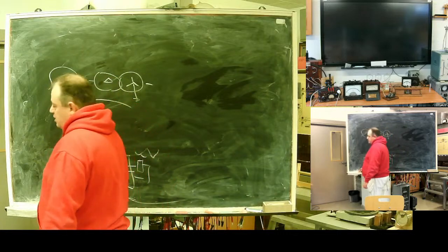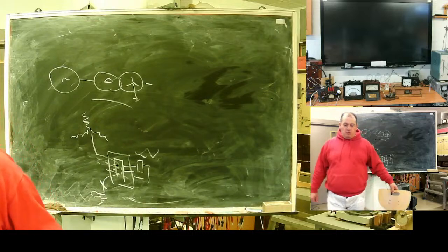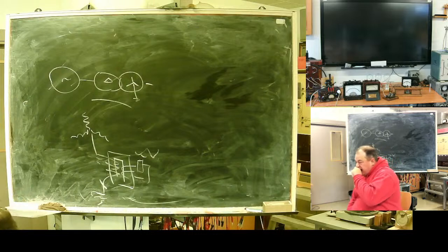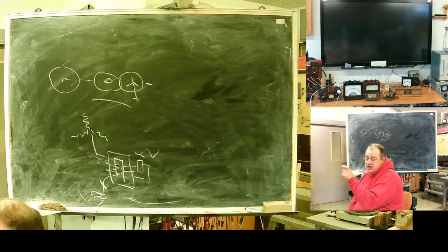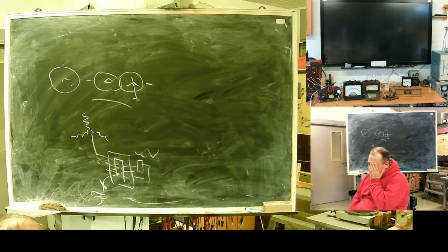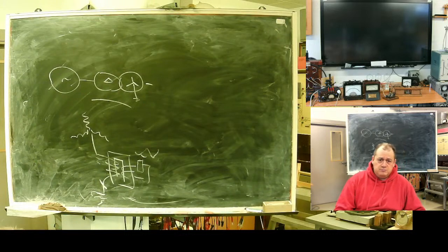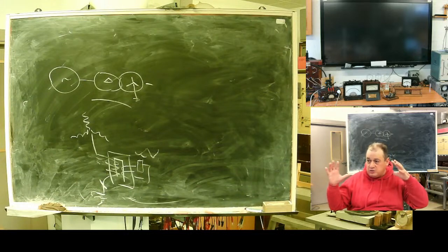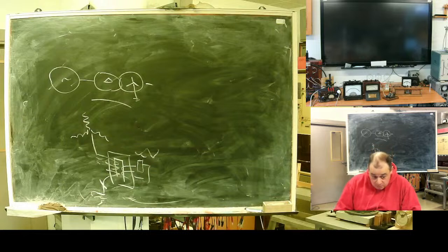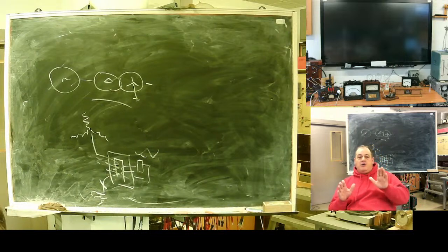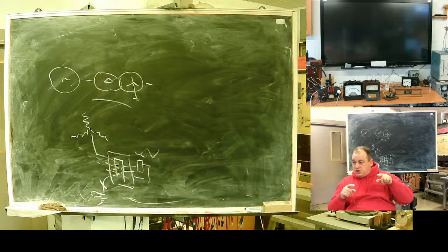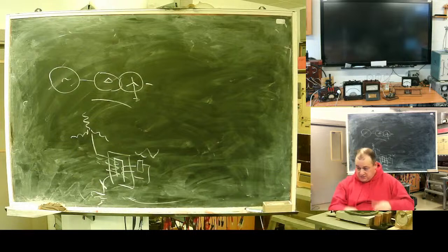The problem is, no one can tell you exactly. For small machines, it can be somewhere from 1/10 of longitudinal reactance to something quite high. Do you know where the problem is? You don't know how the zero sequence flux is circulating. It's a problem of small machines. Old time manufactured machines had cast iron. The shroud was of cast iron with quite good magnetic conductivity, meaning what zero sequence flux, how it can go through direct or negative sequence paths. Because in all windings the flux is the same.